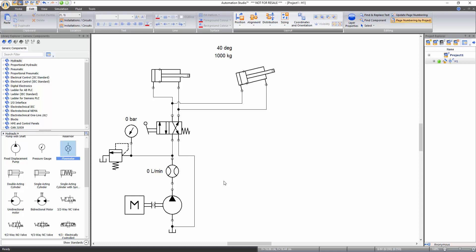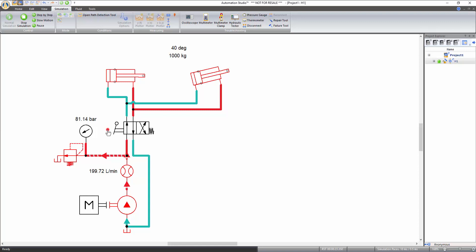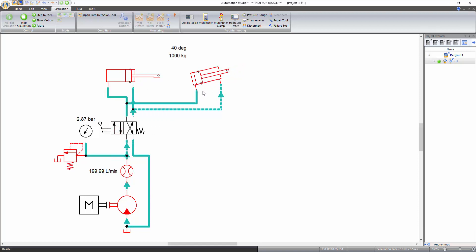Now that measuring instruments have been added, start the simulation to see your circuit come to life. When the position of the directional valve is changed, the cylinder on the left will extend first since there is no load applied to it. The cylinder on the right will extend once the first cylinder is fully extended and the pressure is increased enough to extend the second cylinder, which has an inclination of 40 degrees and an external load of 1000 kg. When the directional valve is changed again, the right cylinder will retract first, followed by the left one.